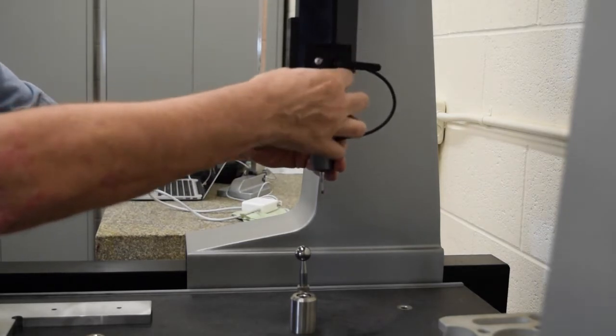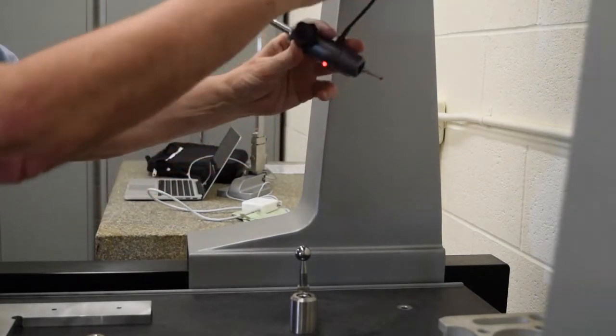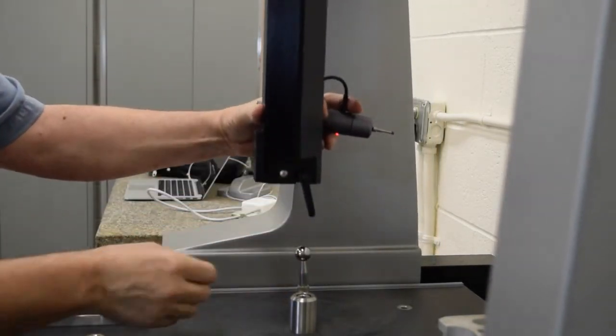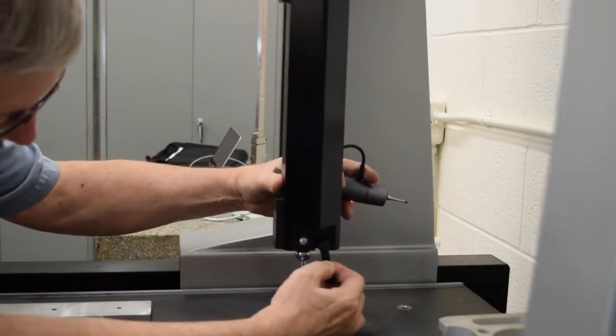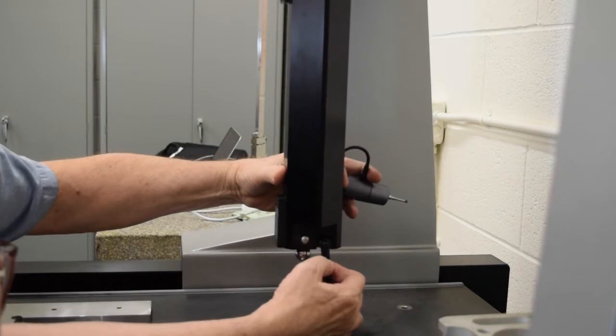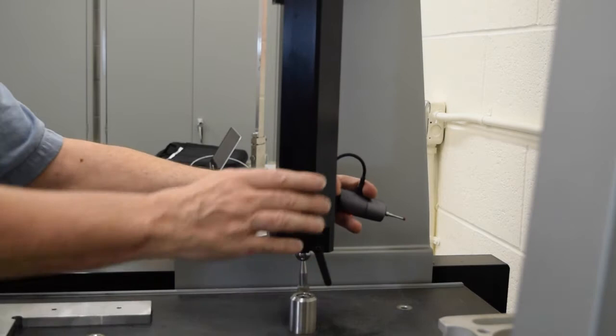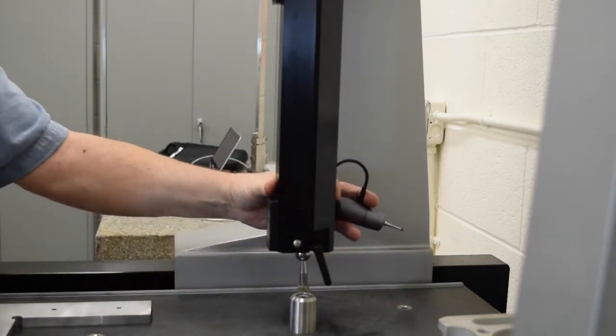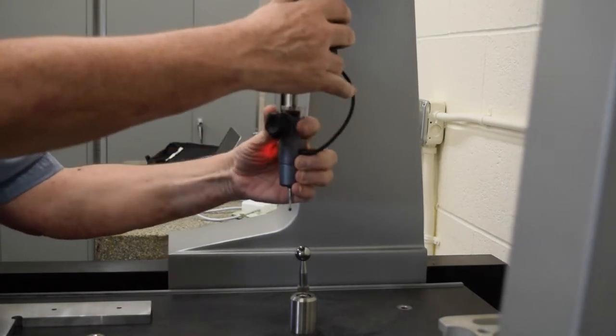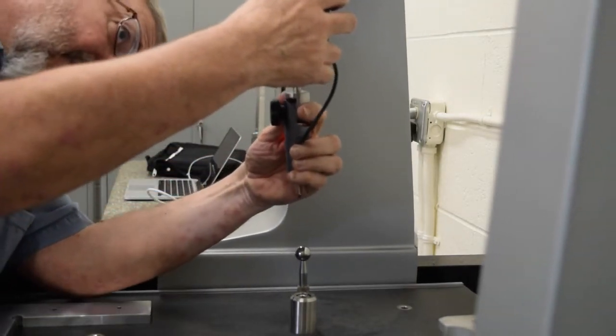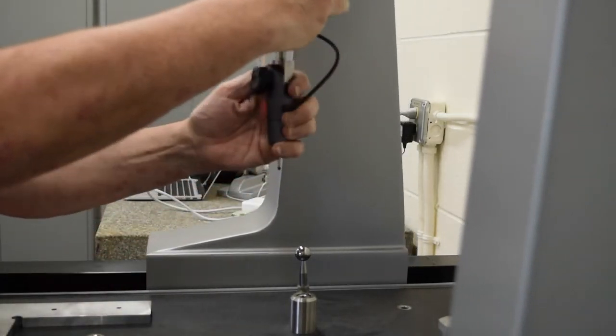Then we remove the probe from the head, and we're going to bring the probe head down to touch the calibration ball, and you're going to line up the hole in the head so that it sits directly on top of the calibration sphere. This will let the machine know exactly where the sphere that we're going to measure in the next step is located. And you notice there that I hit the checkbox that's up on the probe. It's the same button as would be on the console. There's a little checkbox in both places. You can use whichever one is more convenient.